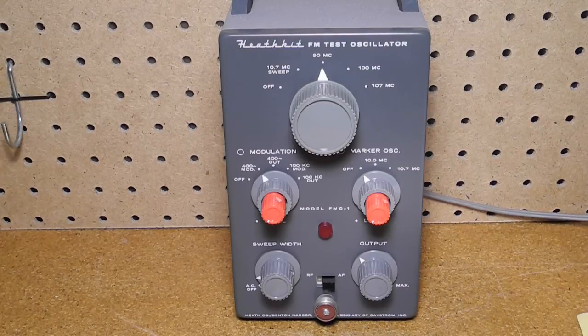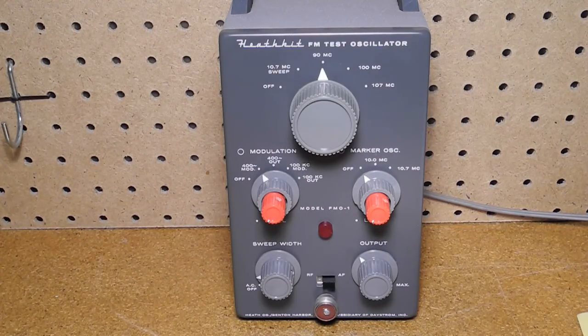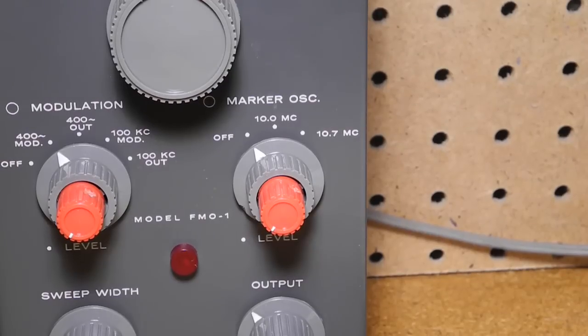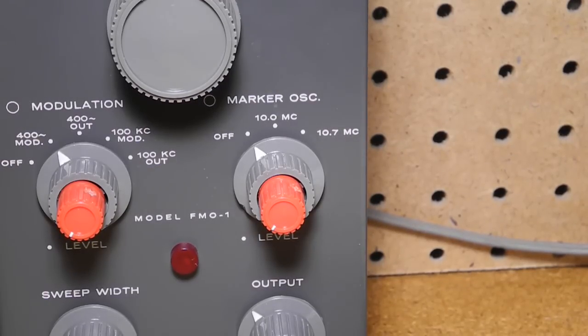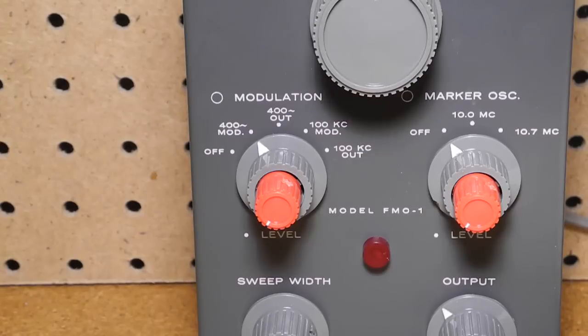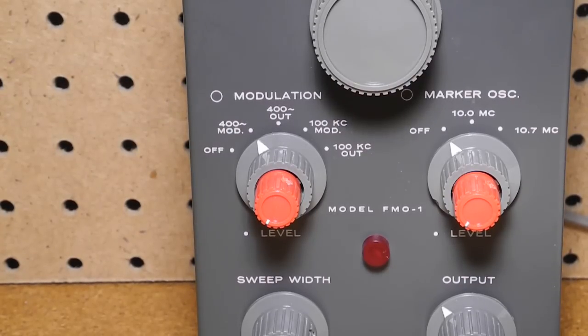The high-frequency oscillator is a Colpitts circuit using one of the triodes, utilizing one of three coils depending on the frequency selected. It can be both frequency and amplitude modulated by the 400 Hz audio. The marker oscillator uses one of the pentodes in a Pierce crystal oscillator circuit. These mix with the sweep signal so they appear as marker pips on an oscilloscope. The audio oscillator is a Hartley circuit that operates at 400 Hz or 100 kHz. The 100 kHz signal is quite distorted from a pure sine wave. This is desired in order to produce harmonics.